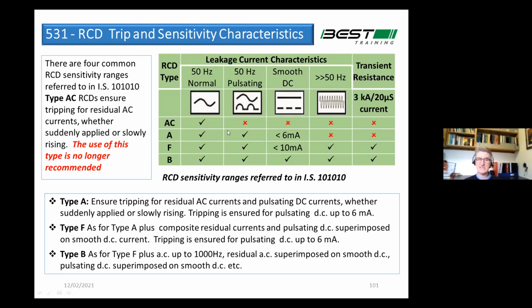So they're really not suitable where you have a lot of leakage current. For that reason, many moons ago, it's not a new thing, I changed my spec back in 2003 or 4 and moved over to type A. And they are resistant to DC up to 6 milliamps. If you know you're going to have more than 6 milliamps of DC leakage current, it will affect the operation of it, so you should be using maybe a type F or a type B. That's all covered in the new wiring rules. It refers to all 4, but it's saying that as a minimum, you really should be using type A now.